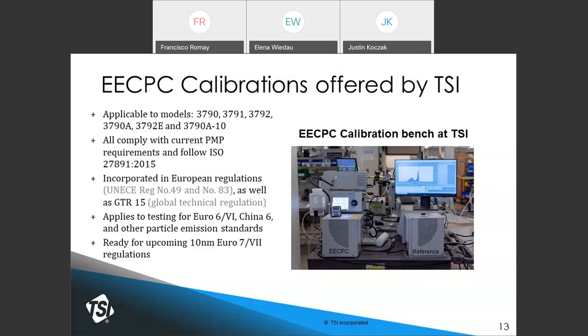TSI also offers calibrations for 10-nanometer EECPCs, which will be required for upcoming Euro 7 regulations. Regarding calibration frequency: CPCs need to be calibrated at least once a year and verified at six months — either verified against a reference or the wick replaced. This is the current requirement.